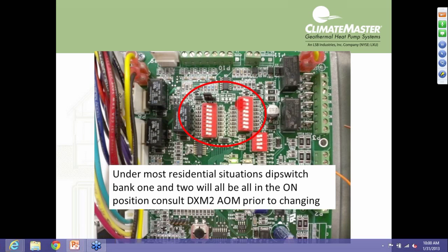Number 7 is for a boiler cooling tower application. If I move that to the off position, once that loop temperature reaches 50 degrees, we're going to go into emergency heat. And if we're using, say in that application, a non-communicating thermostat, there's possibly going to be no indication on the stat that we're in emergency heat until that homeowner gets that electric bill and is going to be very frustrated with you. So again, we want to make sure under most residential applications, these are always in the on position. If you think you need to make an adjustment, make sure you thoroughly understand what that dip switch does, again, looking in the DXM2 installation manual.